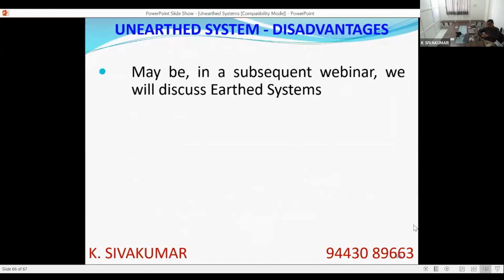So maybe in a subsequent webinar, we will slowly graduate to discussing the various advantages and disadvantages of each method of earthing, like the resistance earthing system. What are the advantages and disadvantages? The reactance earthing system, what are the advantages, disadvantages, and the analysis? Like we have done the analysis for the unearthed system now, we can also do the analysis for the resistance earthed system and the reactance earthed system, that is low reactance earthed and high reactance earthed, which is known as Petersen coil earthing or arc suppression coil earthing. Maybe a month from now we may conduct a second webinar in which we will discuss the earthed systems more elaborately.